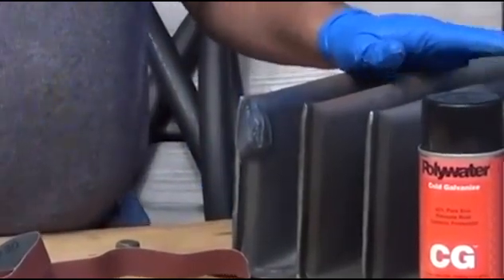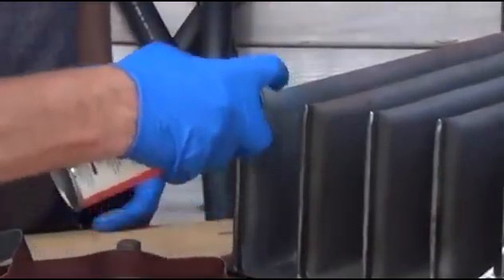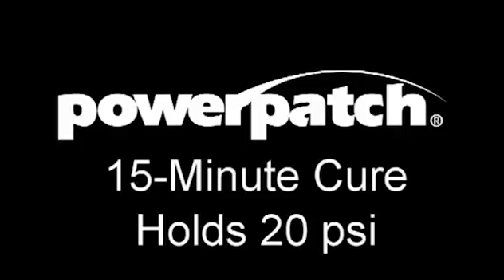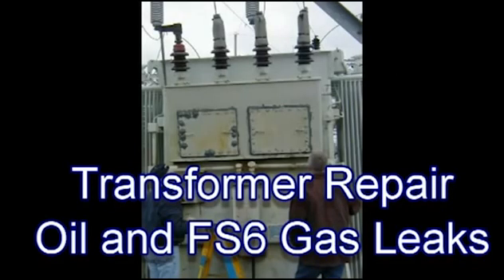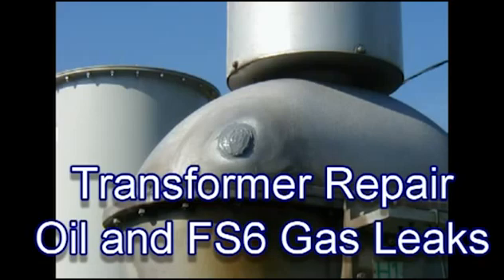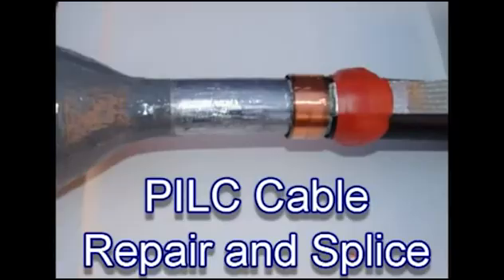The Power Patch can now be painted. After 15 minutes, the Power Patch will hold 20 pounds of oil pressure. When fully cured, Power Patch can hold over 100 pounds of oil pressure. Power Patch can be used for fixing transformer oil and SF6 gas leaks, PILC cable leaks, as well as lead splicing.